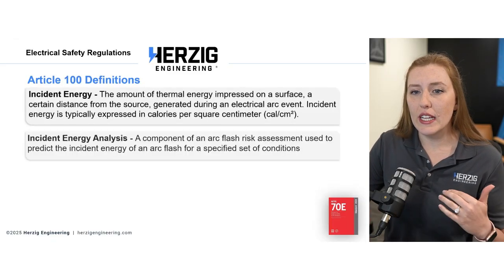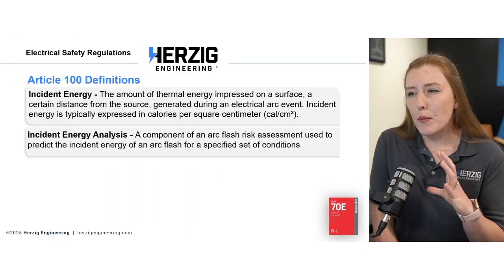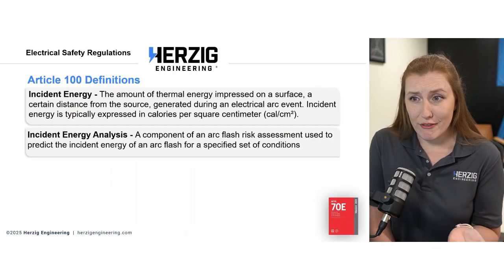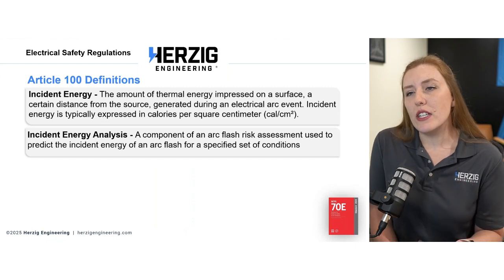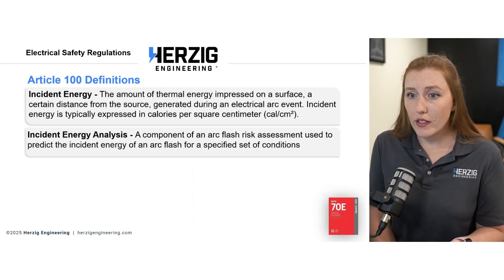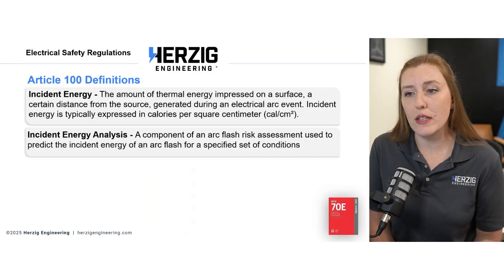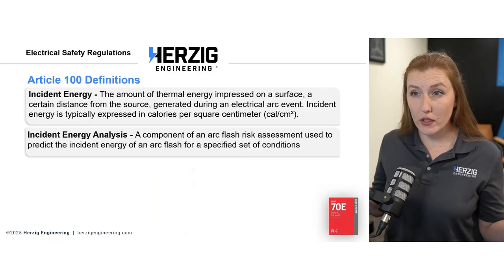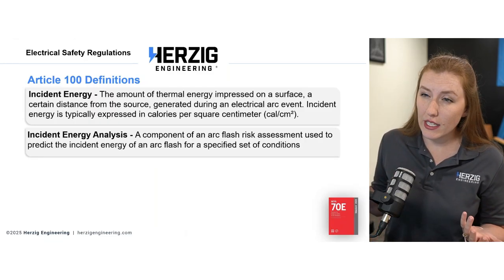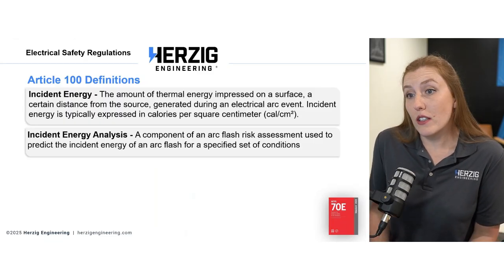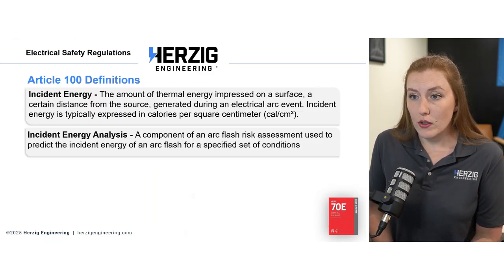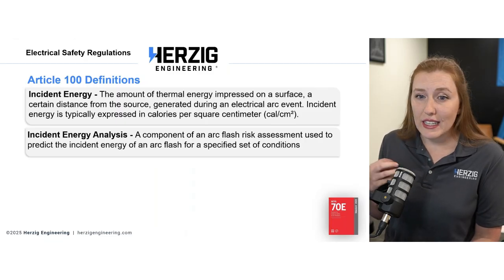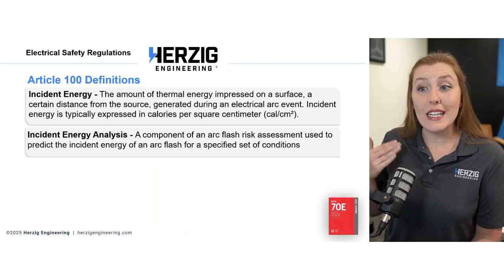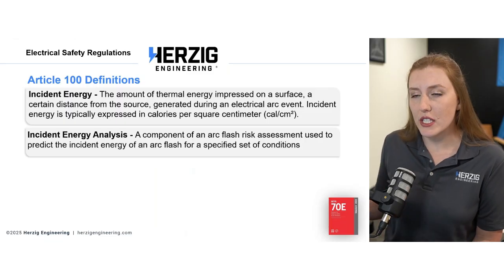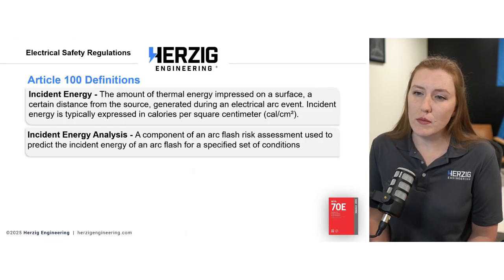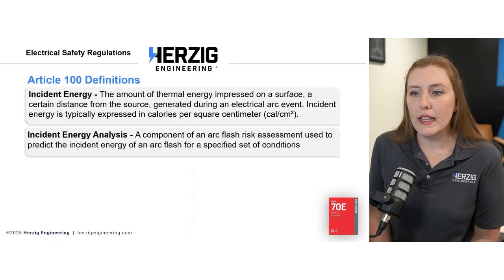Now, incident energy and the incident energy analysis, something to point out is the definition of them. Incident energy is expressed in calories per centimeter squared. It's the amount of thermal energy impressed on a surface a certain distance from the source. For low voltage equipment, that's typically 18 inches. And it's generated, of course, during an electric arc event. So if there's that flashover, if it's ionizing the air and creating that massive and traumatic event, if there is an arc flash, we can measure that or predict that in calories per centimeter squared. Just a little tidbit there.